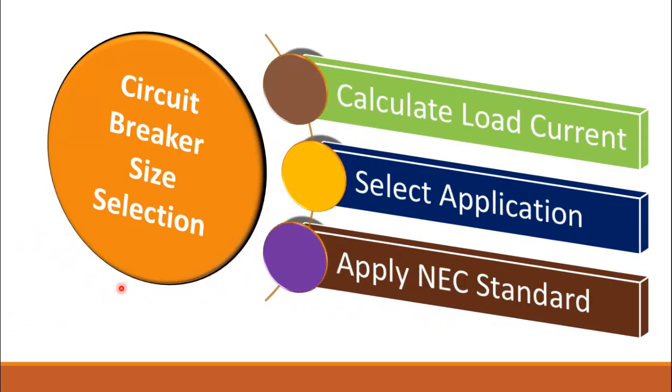Welcome to another video. In this video we'll learn how to properly size the circuit breaker according to our application. The sizing of the circuit breaker means the selection of the ampere rating, because it is the most important selection — it provides protection to your circuit and the load connected to the branch circuit. There are three steps in sizing the circuit breaker: first, compute the load current; after that, select the type of application.